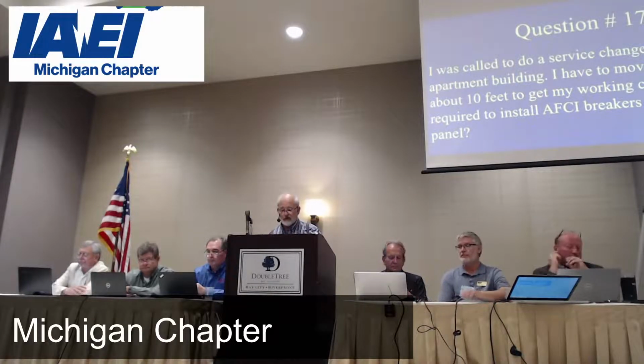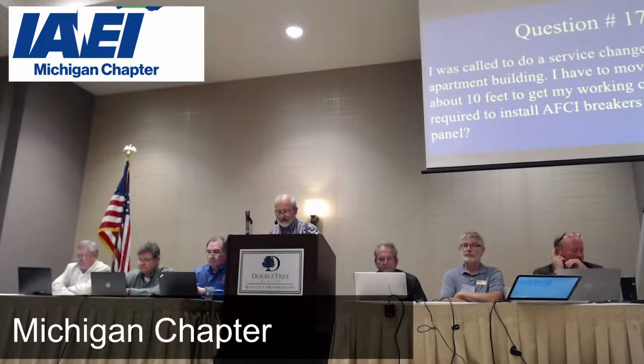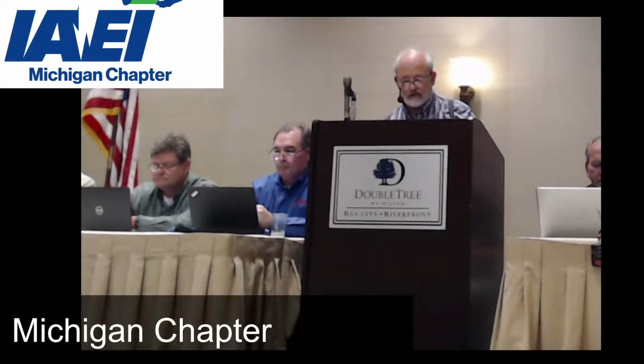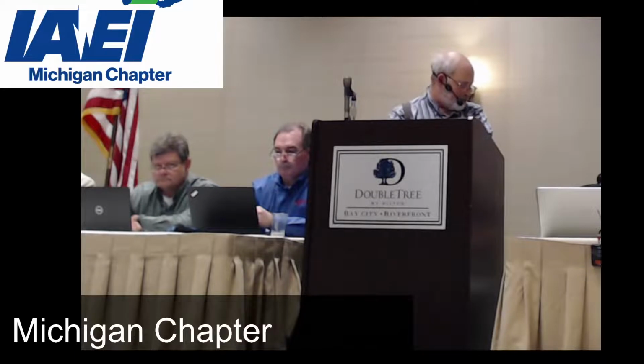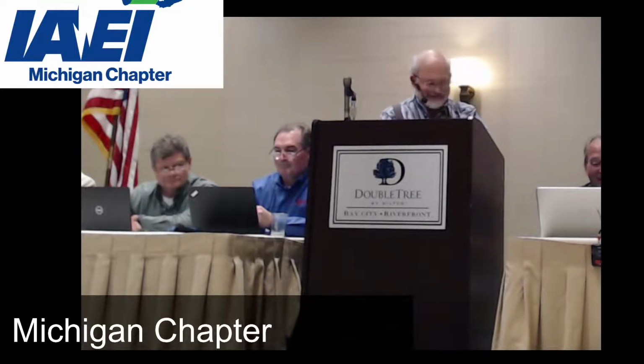Bill, I was called to do a service change on an older apartment building. I have to move the panel board about 10 feet to get my working clearances. Am I required to install AFCI breakers in this new panel? Well, yes, you are. It's important to remember that this is a multi-family dwelling we're concerned with, so that in Michigan, the national code applies and not the MRC.